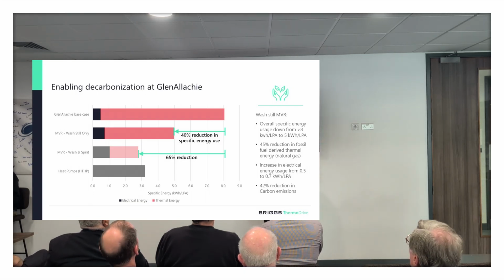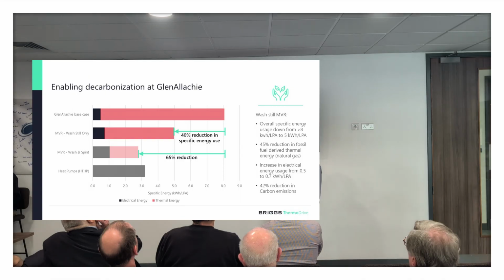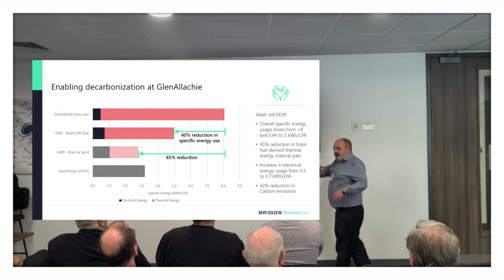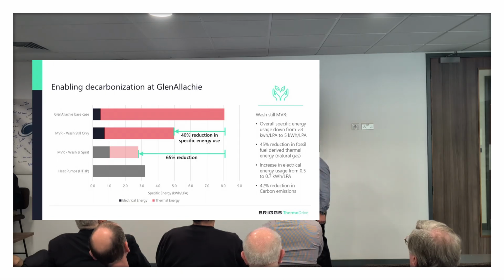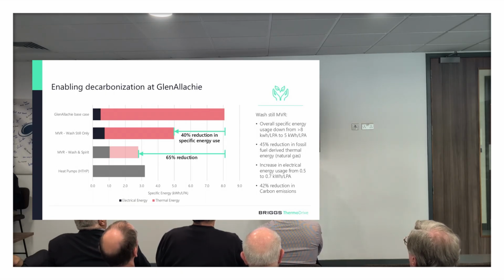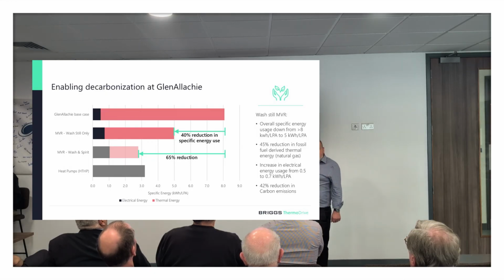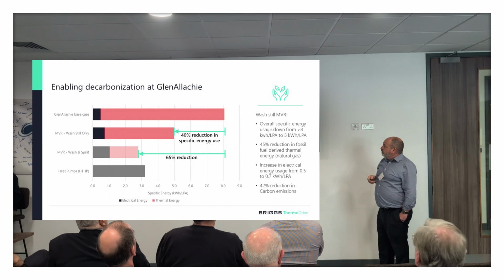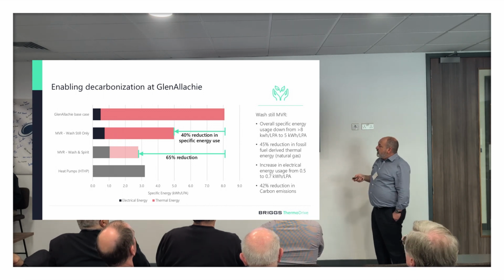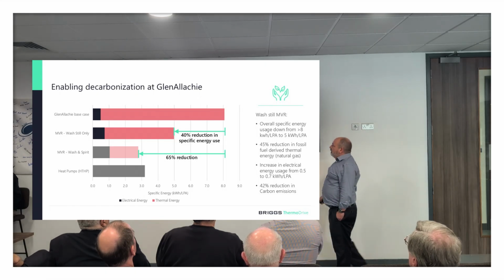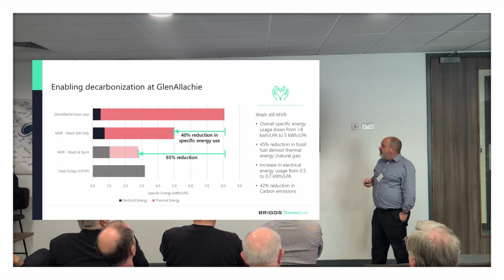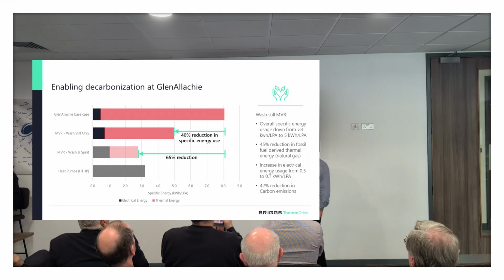They've been told they need to wait 18 months to 2 years before they'll get the electricity to enable them to do that. And they need to wait 3 to 5 years if they were going to go down a high temperature heat pump route with a coefficient of performance of between 2 and 3, which would give them similar savings, but would mean a reduction overall in energy use, but a big increase in their electrical power requirements. So say 2/3 of their energy saved, but without waiting that period of time until we get that big electrical supply.